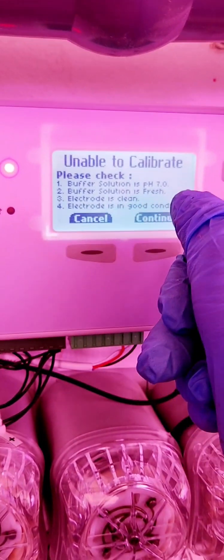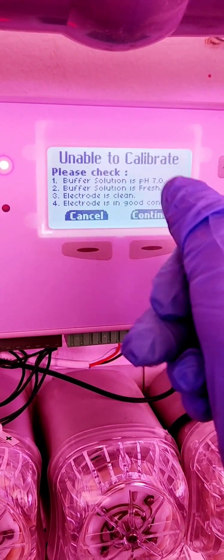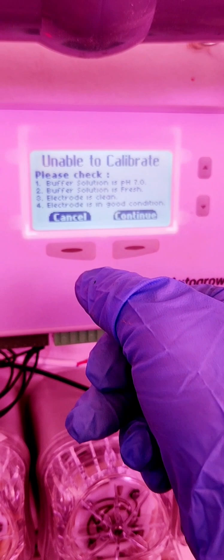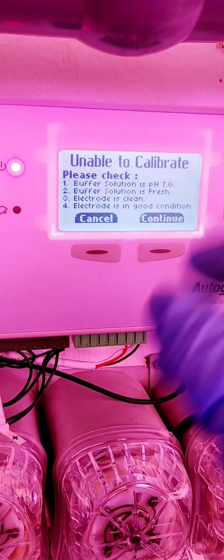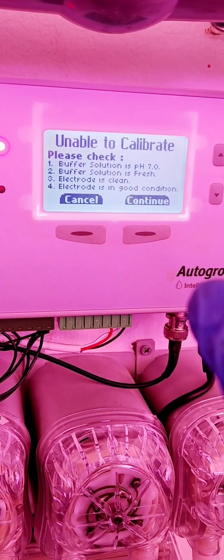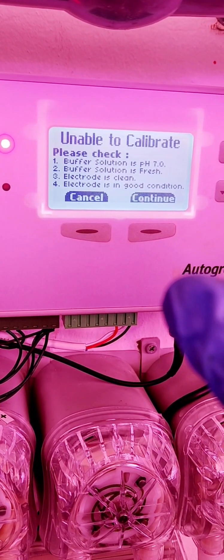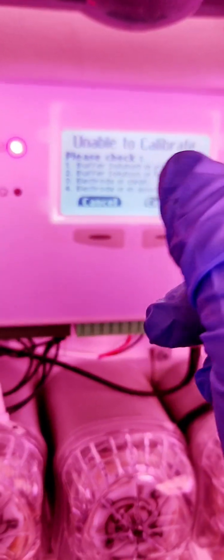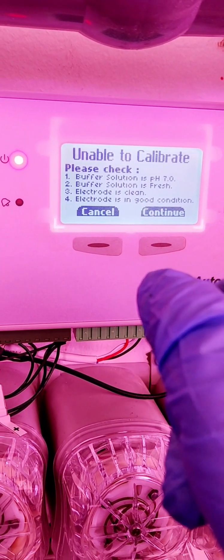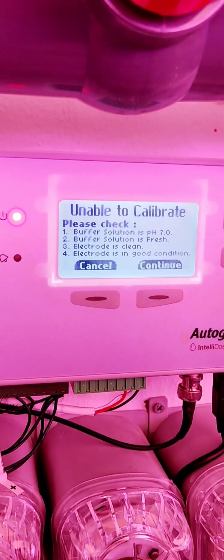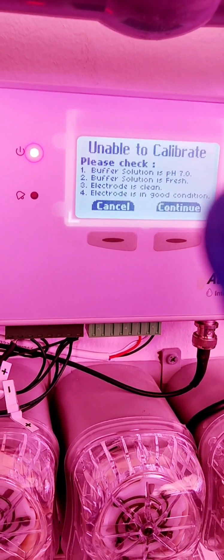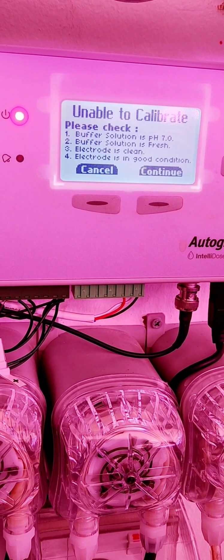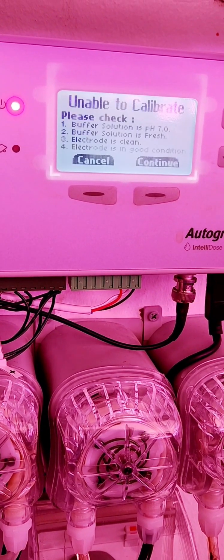Buffer solution is pH 7 is correct. Buffer solution is fresh. Yes. That one is newly bought. Number three. Electrode is clean. Yes. I clean it. I checked also. Possible dirts or any debris. And then I clear it. I clear it off. And then number four. Electrode is in good condition. Yes. Definitely yes. I suspected that previously this has been an issue. I will try to inform the supplier to check on this.